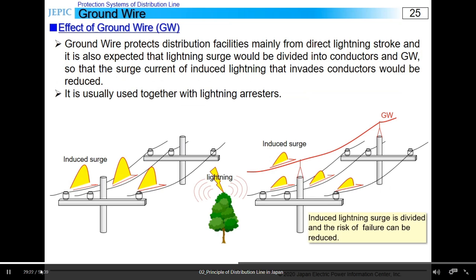Ground wire is usually a steel wire which is installed on the top of the distribution equipment and protects electric poles or lines from direct lightning stroke. Even if the lightning doesn't strike distribution equipment directly, induced lightning surge may cause damage. But it's expected that lightning surge can be divided into conductors and ground wire so that the surge current of induced lightning that invades conductors can be reduced.